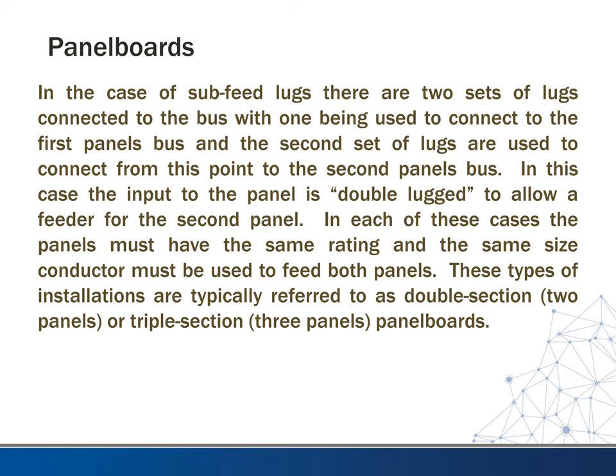In the case of sub-feed lugs, there are two sets of lugs connected to the bus, with one being used to connect to the first panel bus, and the second set of lugs are used to connect from this point to the second panel bus. In this case, the input to the panel is what we call double lugged, and you can do this to a transformer as well, to allow a feeder for the second panel. So when we double lug a transformer, we can feed two loads from the same transformer, same concept.